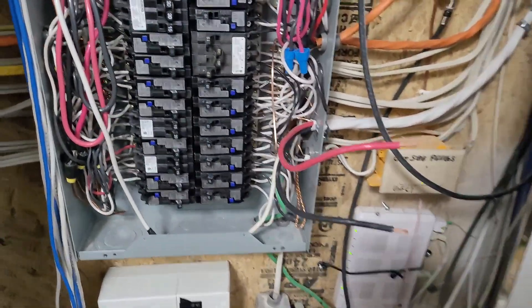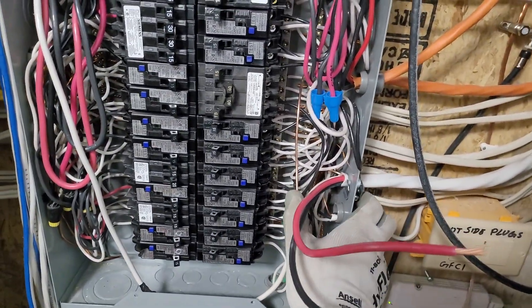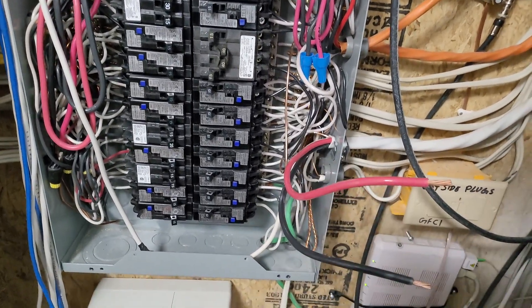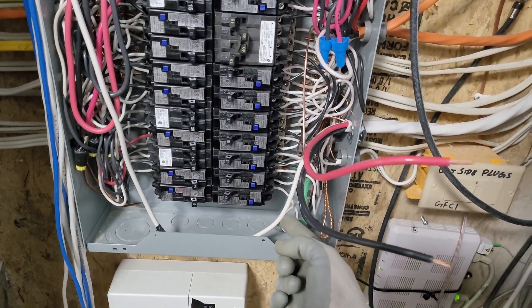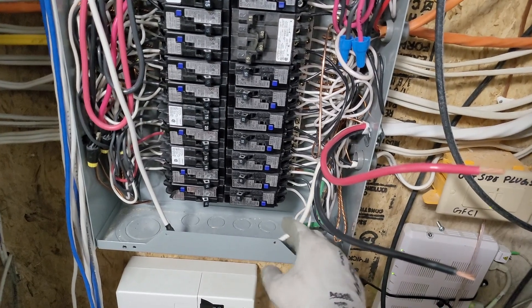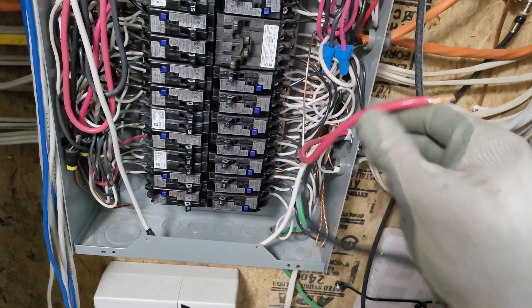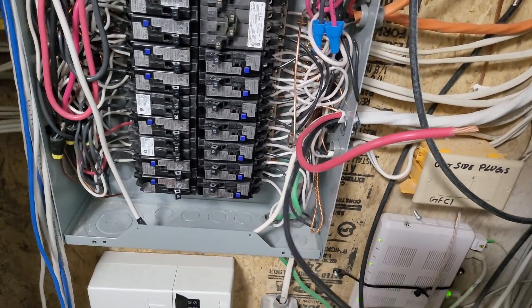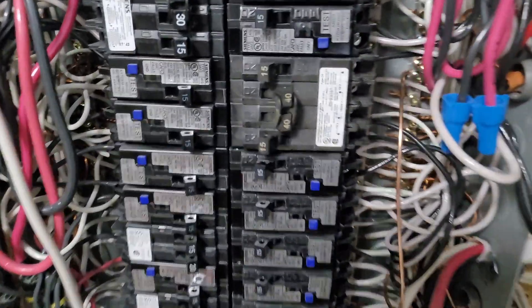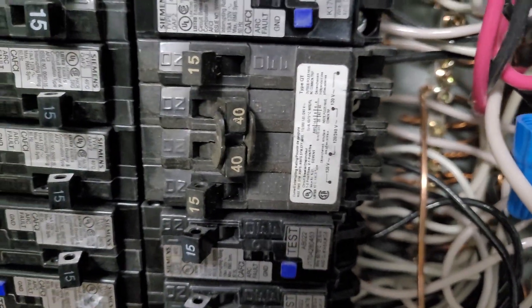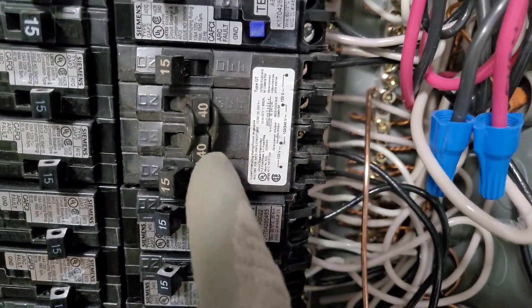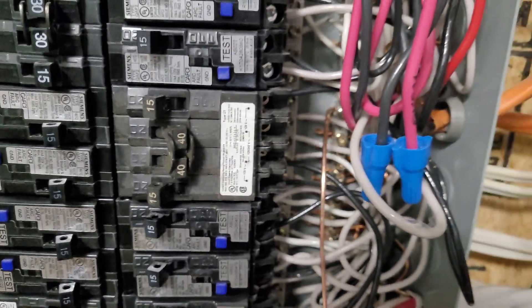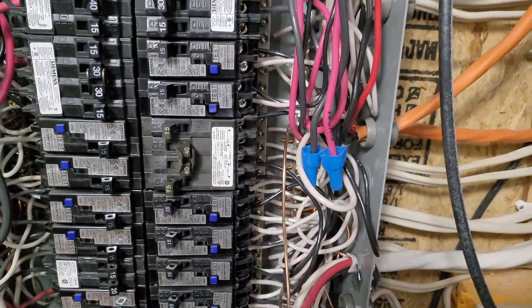The cable's in here. I got it bonded. The white is an extra wire I'm not using. I'm just gonna leave it in here. My red and black, my line one, line two, I'm gonna put it on this 40 amp breaker right here and power it up.